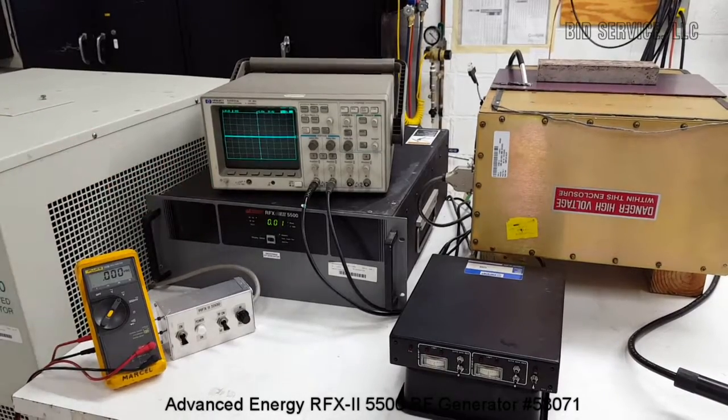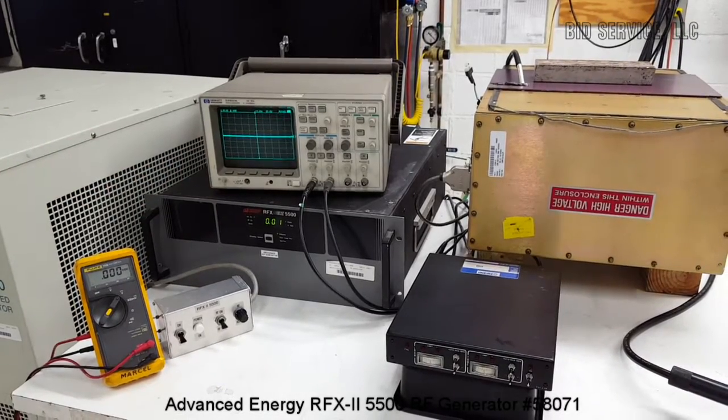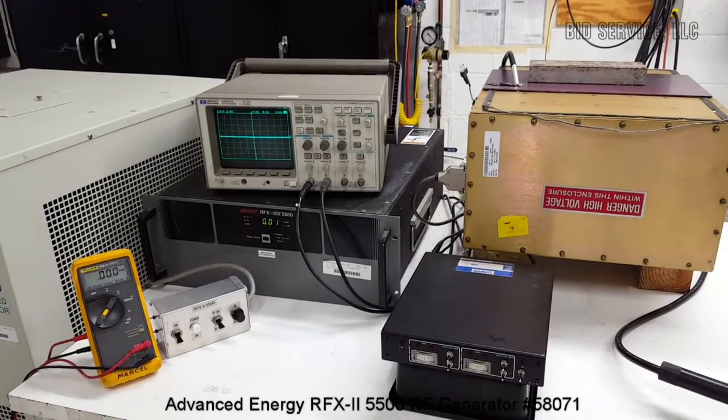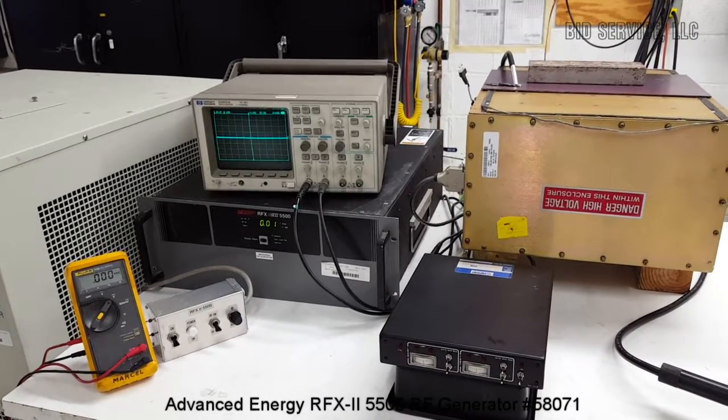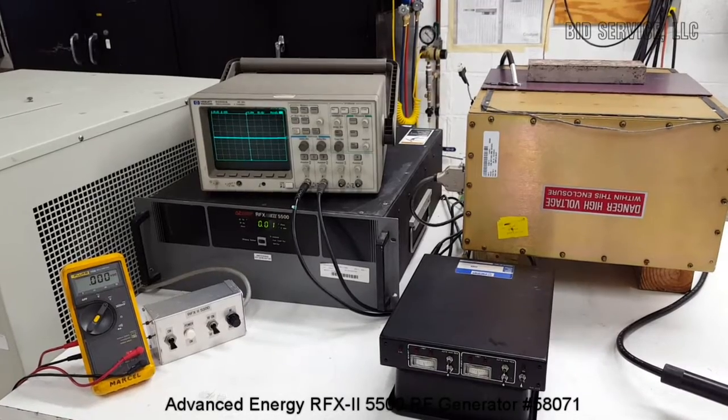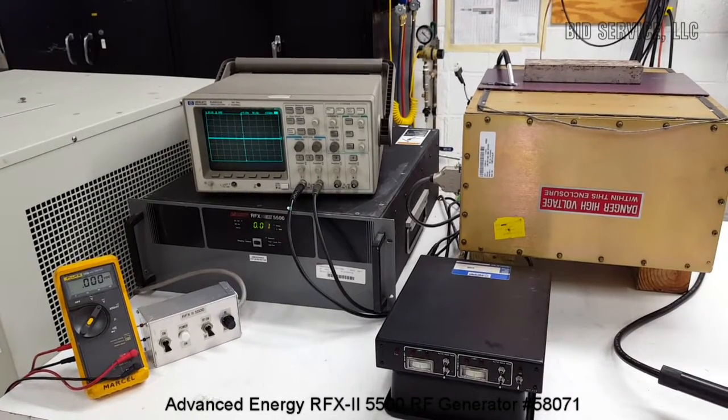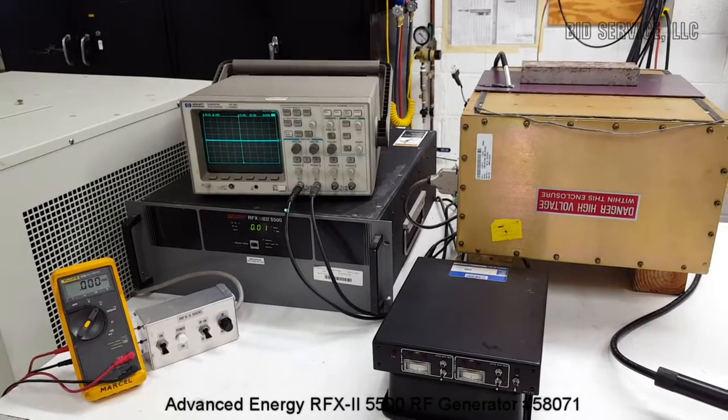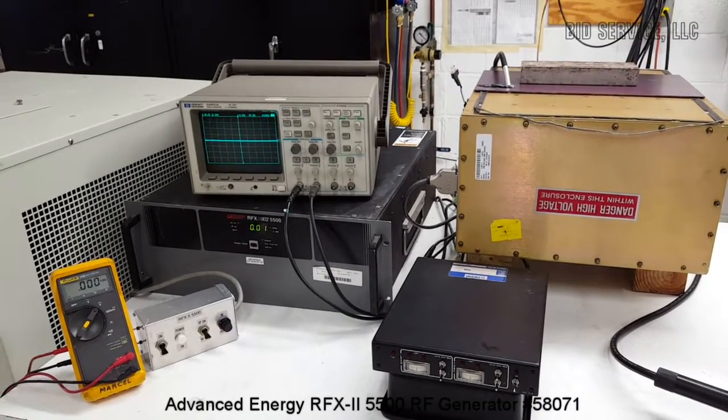It is powered by 208 three-phase requiring a 50 amp service. It is also a water-cooled unit requiring a minimum of four gallons per minute. This 13.56 MHz unit has an output power of between 100 and 5500 watts.